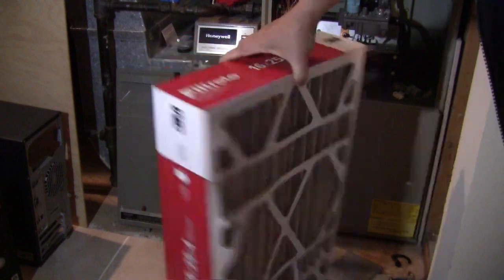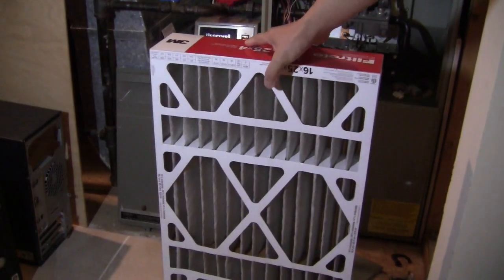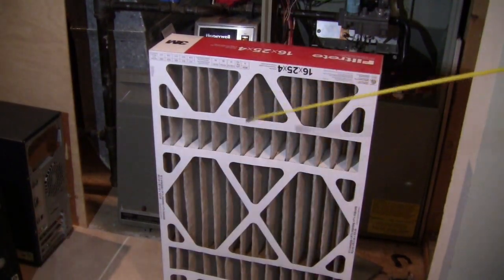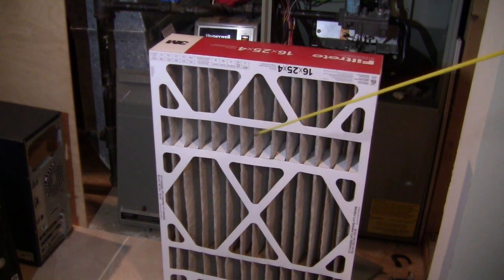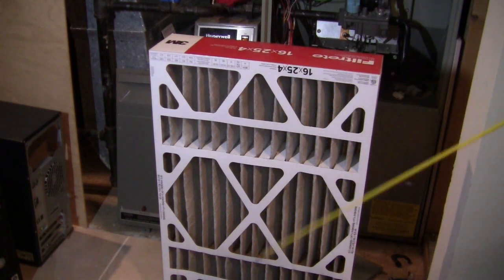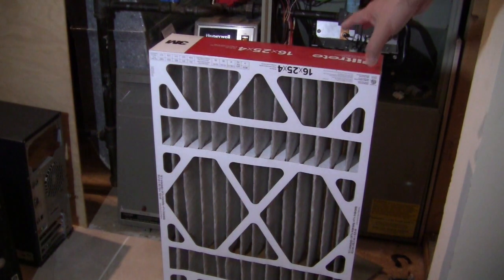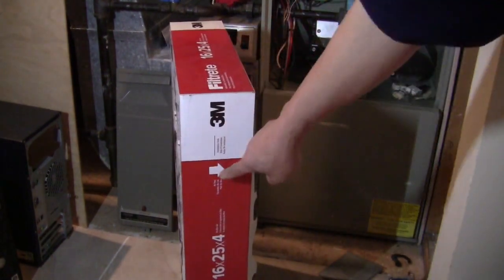But turn to this side. There's no metal here. So if this thing gets broken, it can just fly into the fan and cause damage. Sometimes this damage is very severe, because it can clog your fan, and if the fan gets clogged, the overcurrent is going to burn it up, and you have to replace the fan. So be careful. If you do replace this, pay a little bit of attention to this.